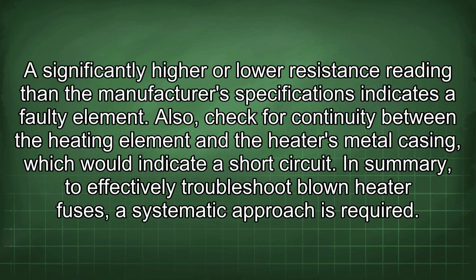A significantly higher or lower resistance reading than the manufacturer's specifications indicates a faulty element. Also, check for continuity between the heating element and the heater's metal casing, which would indicate a short circuit. In summary, to effectively troubleshoot blown heater fuses, a systematic approach is required.